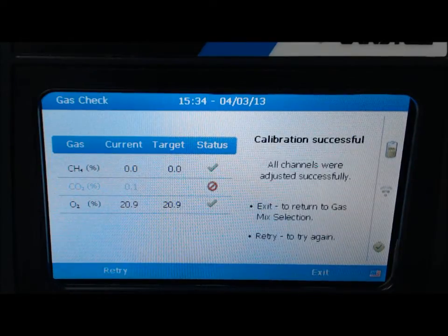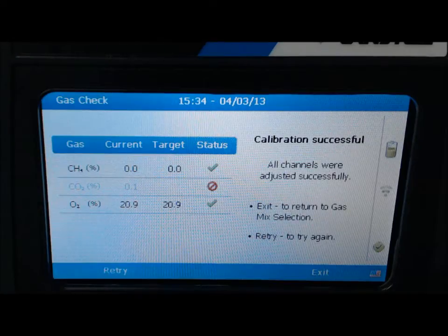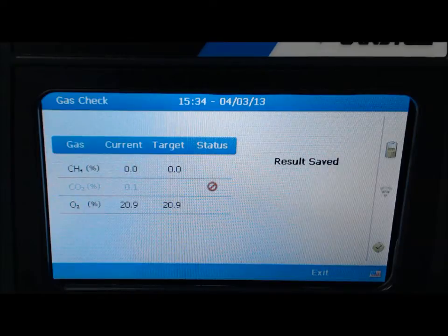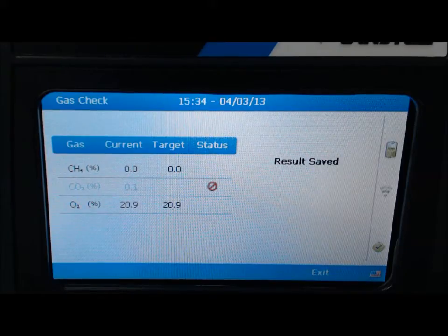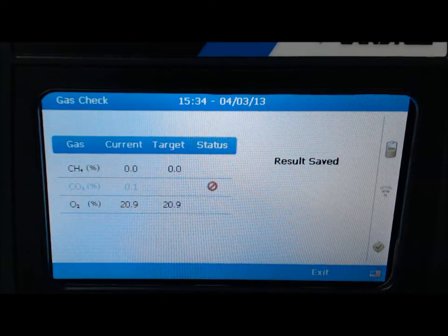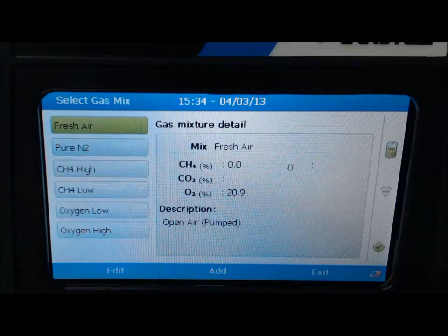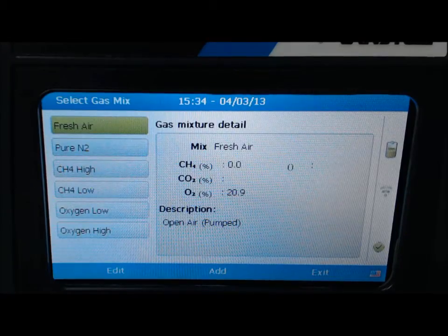Note calibration results and select retry or exit to continue. Select exit to save the results and select exit once again to continue. This should take you to the select gas mix screen.